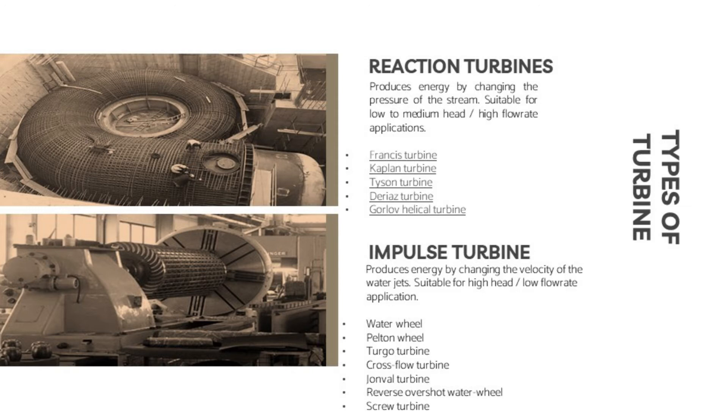For reaction turbines, they produce energy by changing the pressure of the stream, suitable for low to medium head, high flow rate applications. The reaction turbines are Francis turbine, Kaplan turbine, Tyson turbine, Deriaz turbine, and Gorlov helical turbine. The Francis turbine is actually a reaction turbine plus impulse turbine because the shape of the blade has a curve that will change the velocity of the stream, so it can be categorized as both.